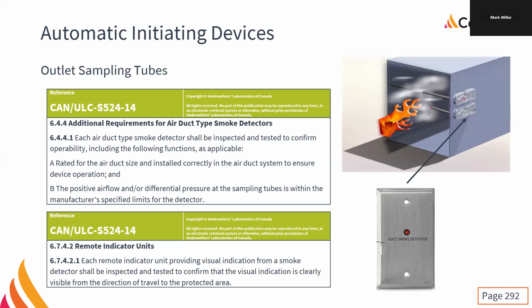vast majority of the time, these duct smokes are up in a ceiling somewhere. You can't see them from the ground, and when you have a device that you can't see from the ground, we need a remote indicator. Even in mechanical rooms, we often need to put remote LEDs in because the duct smoke could be so high up and there could be so much piping and ductwork and all that stuff up there. You might not be able to see it from the ground. You might have arrows that people have written over the years on how to find it.